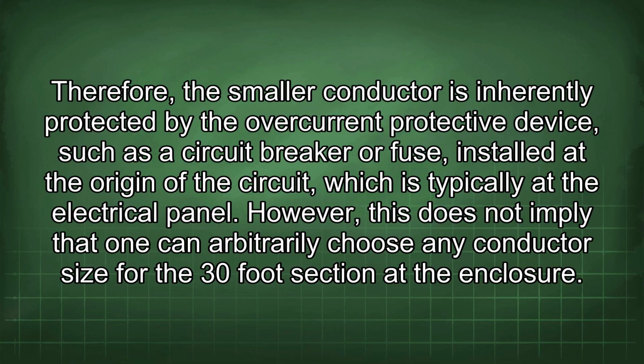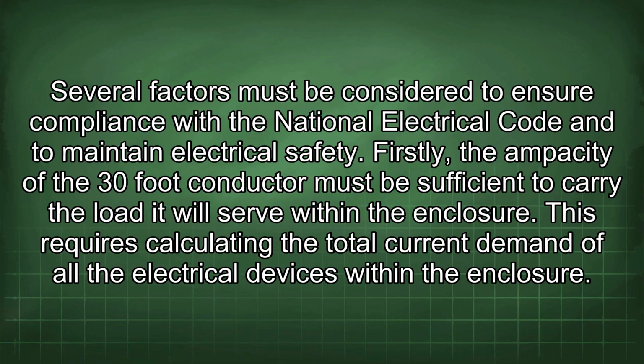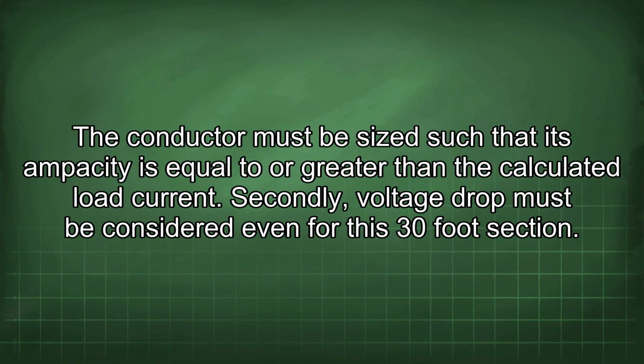However, this does not imply that one can arbitrarily choose any conductor size for the 30-foot section at the enclosure. Several factors must be considered to ensure compliance with the National Electrical Code and to maintain electrical safety. Firstly, the ampacity of the 30-foot conductor must be sufficient to carry the load it will serve within the enclosure. This requires calculating the total current demand of all the electrical devices within the enclosure. The conductor must be sized such that its ampacity is equal to or greater than the calculated load current.